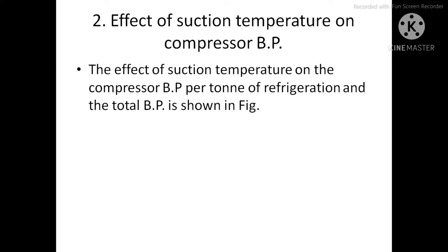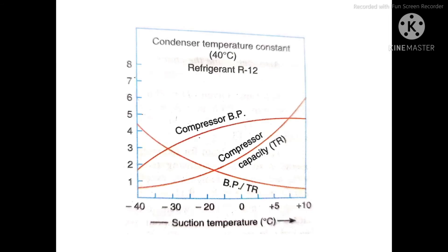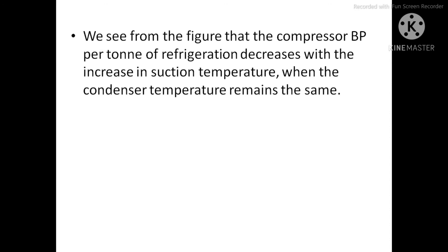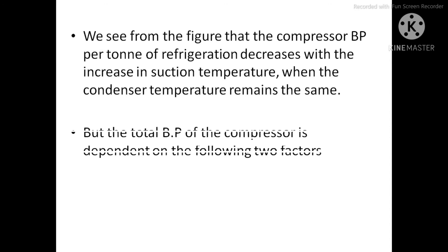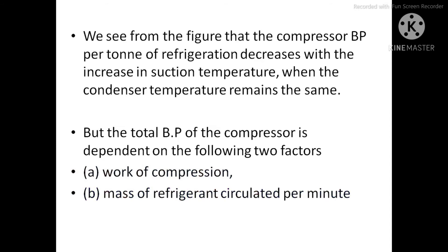The effect of suction temperature on compressor brake power per ton of refrigeration and total brake power is also shown in the figure. With an increase in suction temperature, the brake power per ton decreases. The total brake power of the compressor depends on two factors: the work of compression, and the mass of refrigerant circulated per minute.